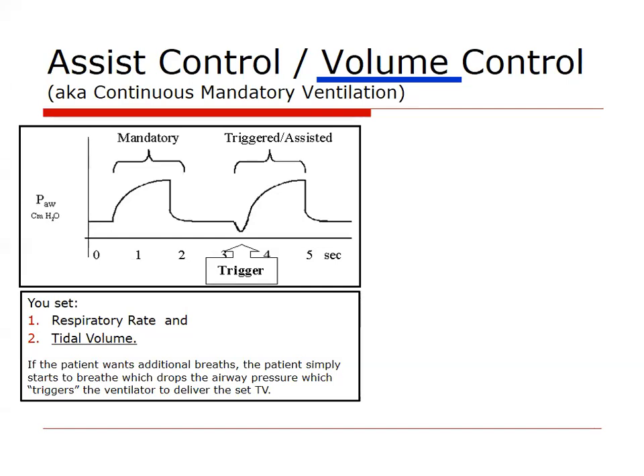In ACVC, if the patient wants an additional breath, a frequency above the set rate, so if you set the rate at 12 but they want a 13th breath in that minute, they can get it and the machine will assist them. How the machine knows the patient wants another breath is that the patient breathes. That movement of the chest creates a little negative deflection in the pressure, and that triggers the machine to push in the same size tidal volume it was going to push in a moment later anyway. So the patient always gets the set tidal volume. That's why we like to start with it. It's not very variable: the patient always gets that tidal volume, either because it was time based on the set rate, or because the patient asked for a breath.